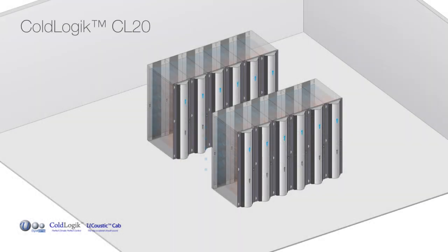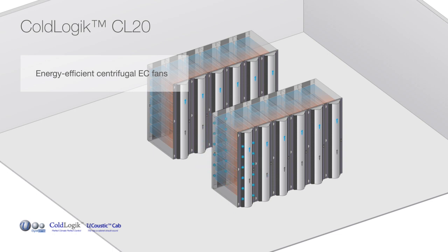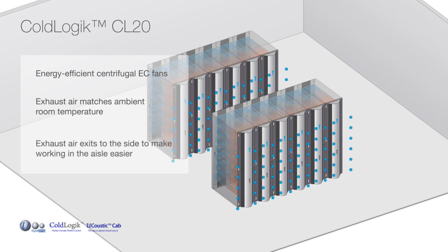The active equipment fans pull the ambient air in through the cabinet, gaining in heat as it does so, before being exhausted onto the inside face of the CL20 cooler. Energy-efficient centrifugal EC fans, mounted within the cooler, pull the warm air over and around a coolant-filled coil and into a plenum chamber, before being passed back into the data center at the predefined ambient temperature. Note how the air leaving the door exits to the side and does not blow directly into the aisle where you or a colleague may be working.